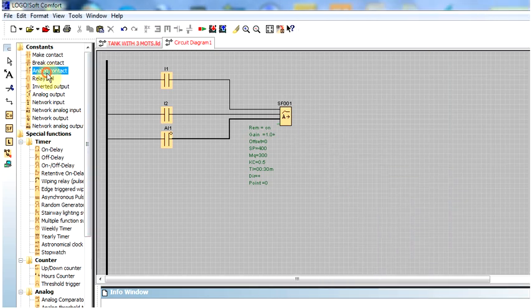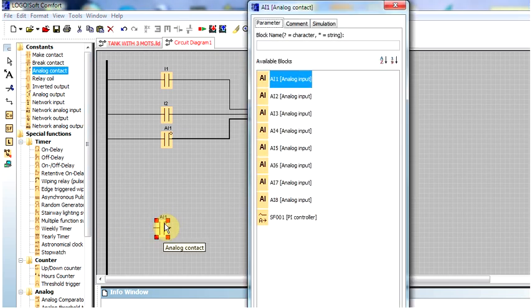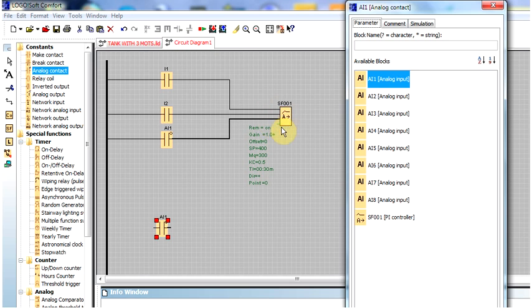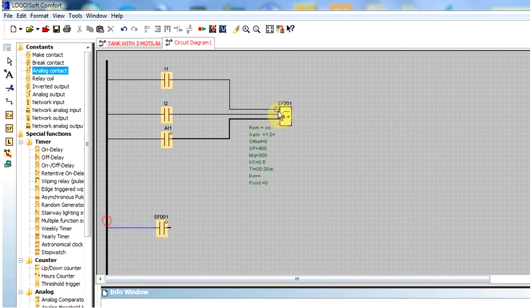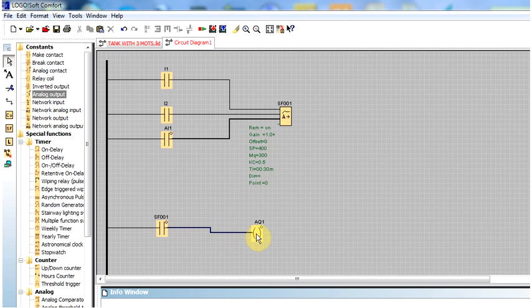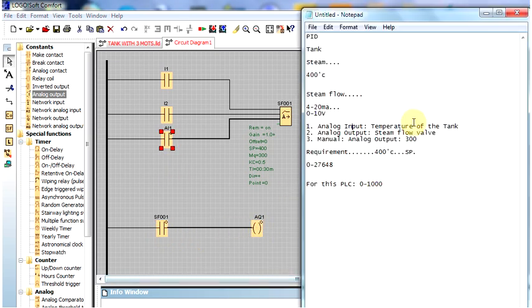For the analog output, I am taking an analog contact here, but I will replace the direct connection because I will not put the analog value directly. Instead, this PID function will calculate and put the analog value. I press the PID controller block — this will take the value from the function and the final result goes to the analog output. So: analog input reads tank temperature, analog output gives the command to the steam flow valve to control the temperature at 400 degrees centigrade.